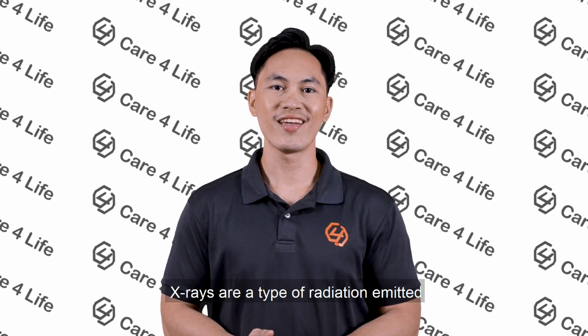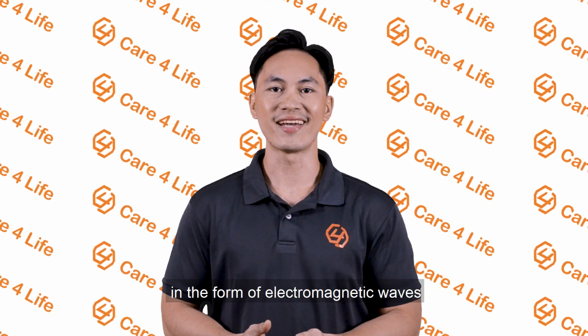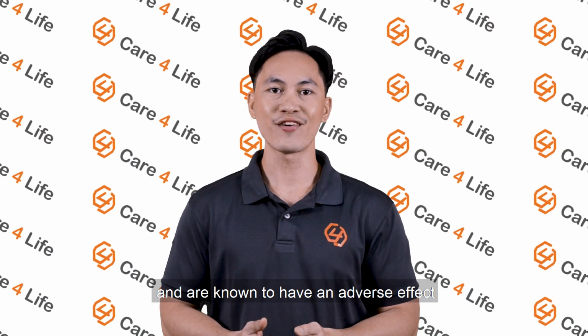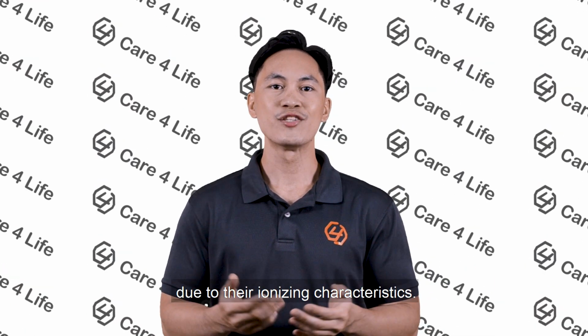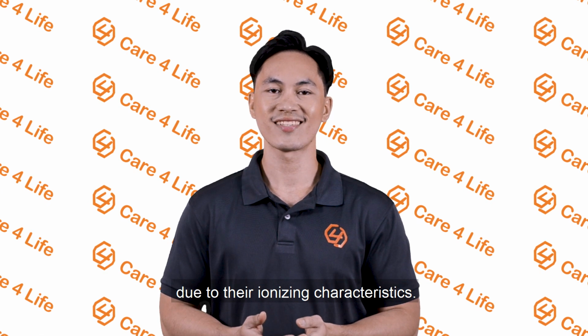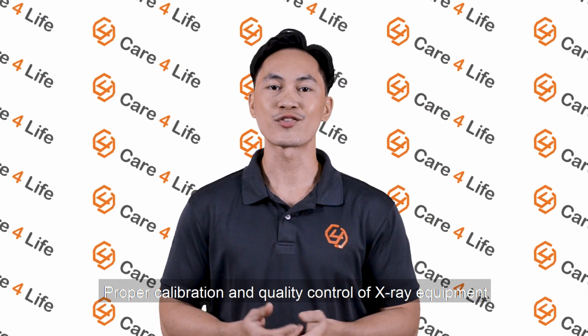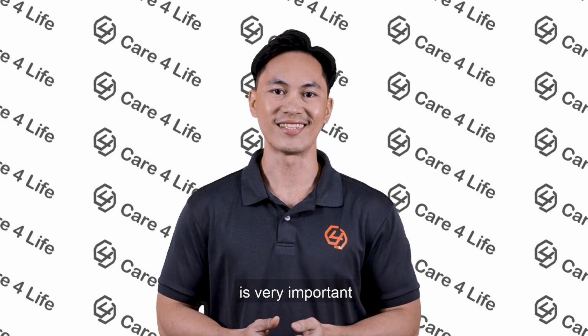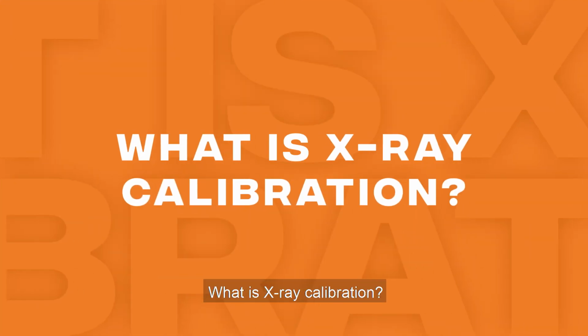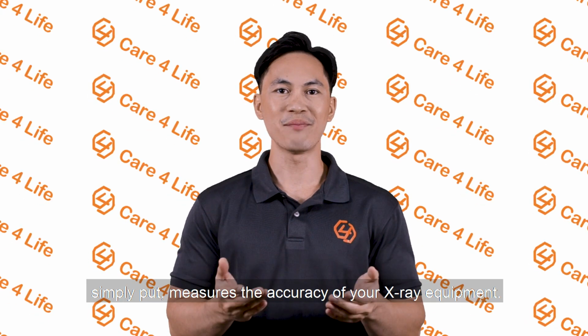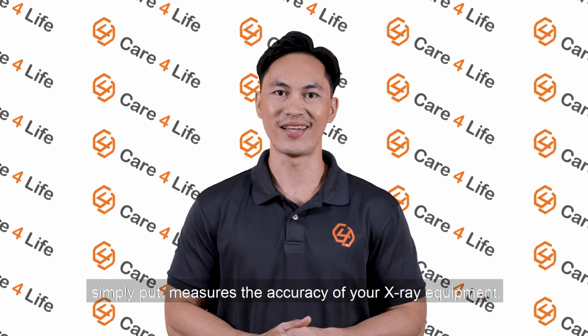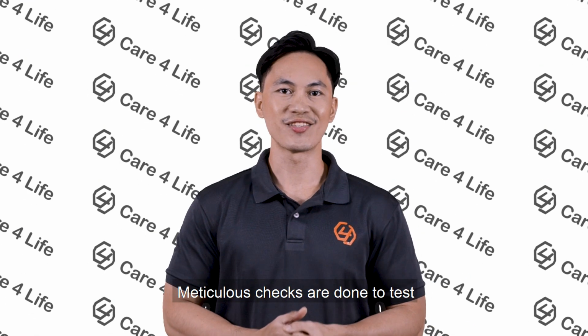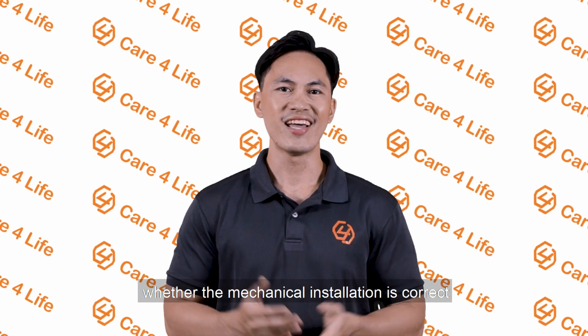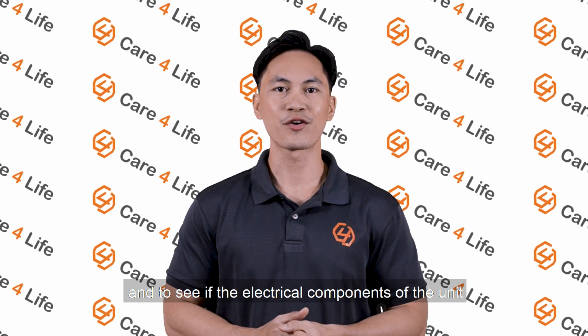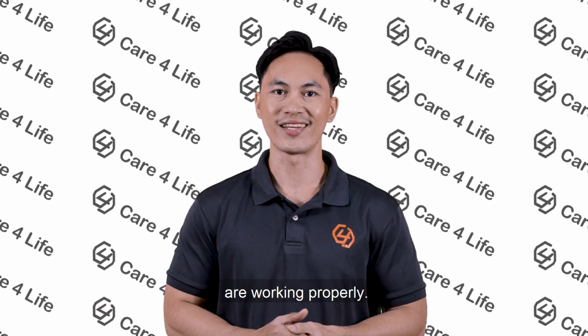X-rays are a type of radiation emitted in the form of electromagnetic waves and are known to have an adverse effect on living organisms due to their ionizing characteristics. Proper calibration and quality control of X-ray equipment is very important. What is X-ray calibration? An X-ray calibration service, simply put, measures the accuracy of your X-ray equipment. Meticulous checks are done to test whether the mechanical installation is correct and to see if the electrical components of the unit are working properly.